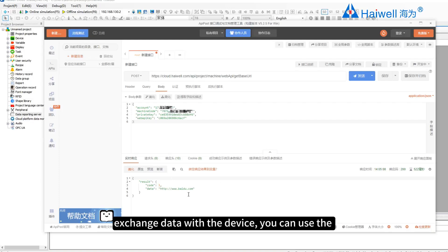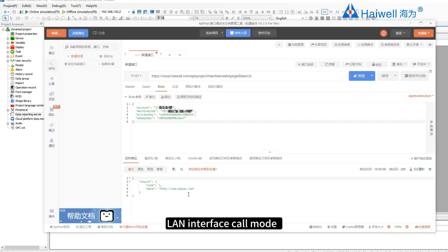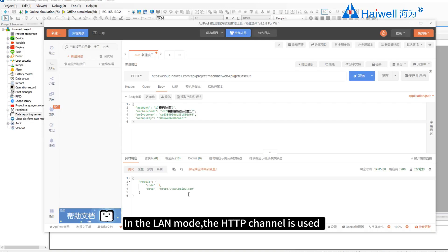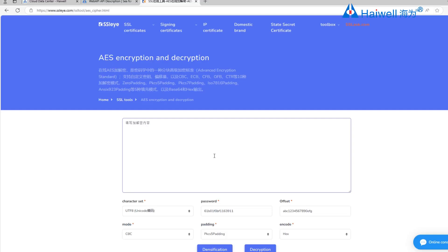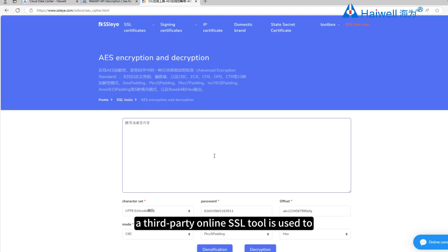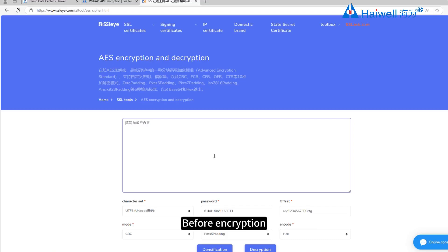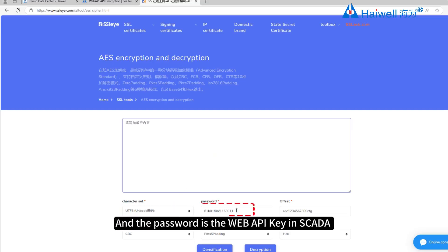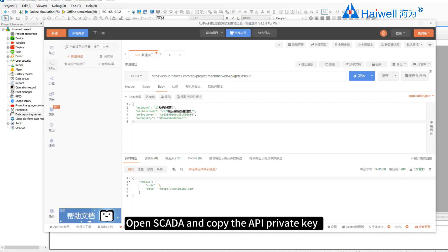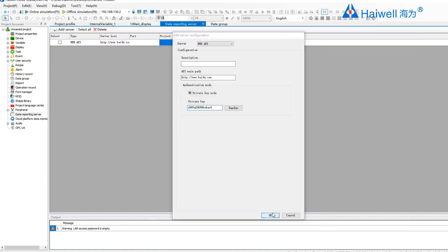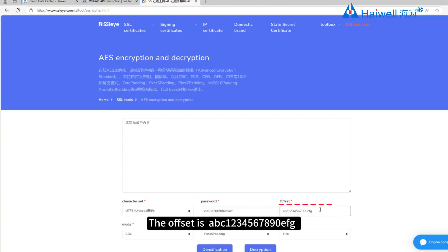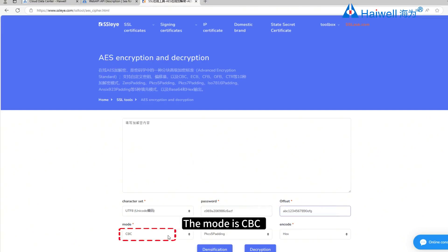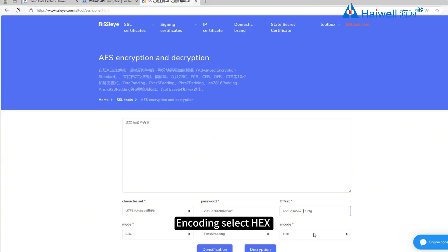If the internal system of the enterprise needs to exchange data with the device, you can use the LAN interface call mode. In LAN mode, the HTTP channel is used. For security, the data needs to be encrypted and the request validity verified. In this example, a third-party online SSL tool is used to encrypt parameters. Before encryption, set the encryption mode character to UTF-8, and the password is the Web API key in SCADA. Open SCADA and copy the API private key.